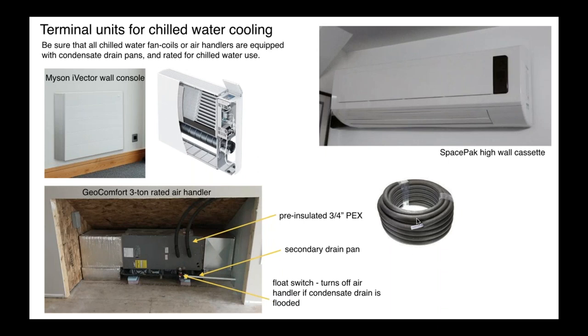You have to pay attention to the details. If humid air can get to a surface that's below the dew point, and on a hot, humid day that dew point could be up in the lower 70s, you're going to get condensation. And if that piping goes over a drywall ceiling, you're going to see streaks on that ceiling. So if you want to get involved with chill water cooling, make sure you come up with a good insulation system. And a typical elastomeric foam is commonly used.